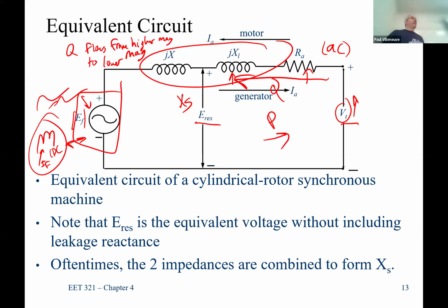You always look at the magnitude, whichever is the higher one - the reactive power should be flowing from the higher to the lower. So even though this is a generator and P is going out, I can still have a higher magnitude voltage on the terminal than inside, and there's nothing wrong with that. That works perfectly fine for my generator.